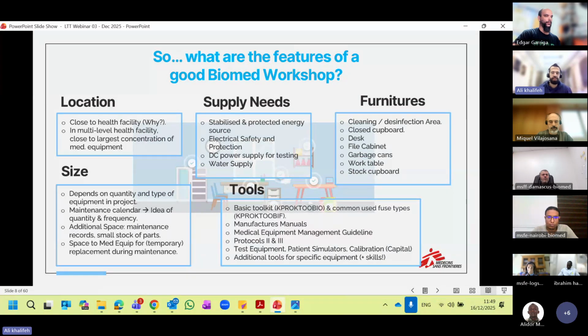We need dedicated equipment like the patient monitor and patient simulator. For other equipment, we need a ventilation analyzer for the anesthesia machine or ventilator, an oxygen purity sensor reader to read the oxygen purity of a concentrator, and a manometer to test the pressure. Depending on our inventory, we can recommend this test equipment. The main problem is that it is very expensive and needs calibration yearly or every 2 years. So we recommend having at least one kit in the capital, which could be used by the biomedical focal point whenever needed.